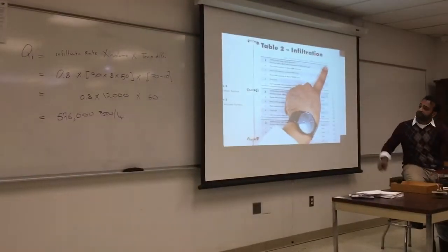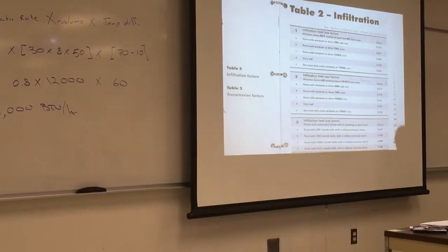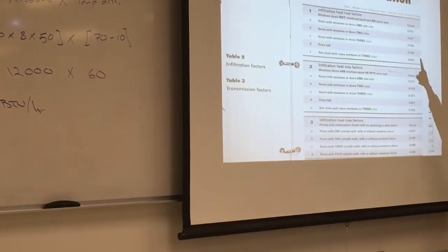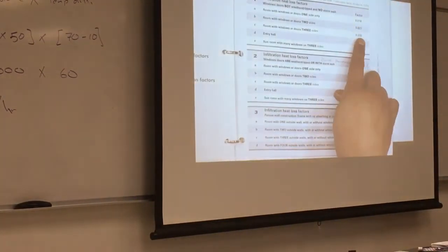So we have 3 sections, right? And they're all the same. And this gives you number of air exchange per hour, infiltration factor divided by 0.018. So that's a conversion between the heat air capacity from minute to hour, but they did the math for you. So that's going to be your infiltration rate here.